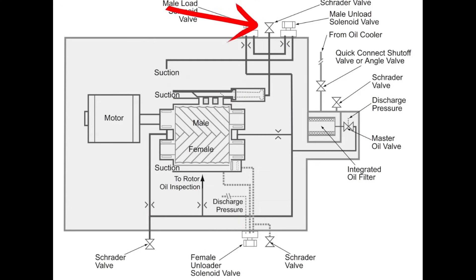At startup, this will be in a fully unloaded state and your unload solenoid will be activated. So that if this, for some reason, was loaded at shutdown, it can unload. But until the female unloader is energized and closed and the system is ready to begin loading, which this takes a few minutes sometimes depending on chill water conditions, these will not begin to load.